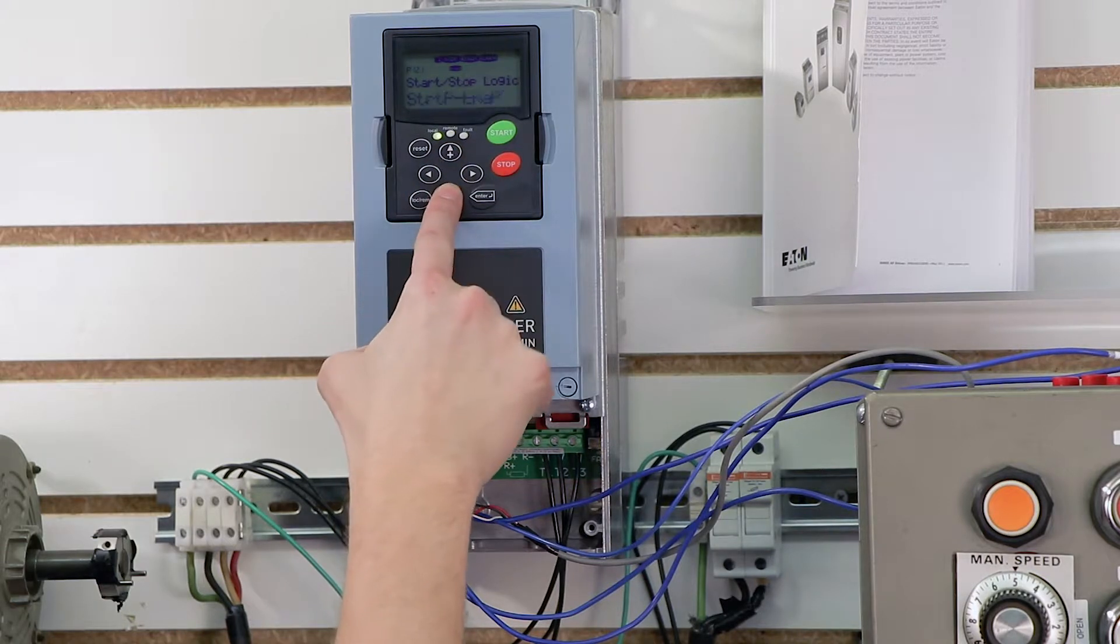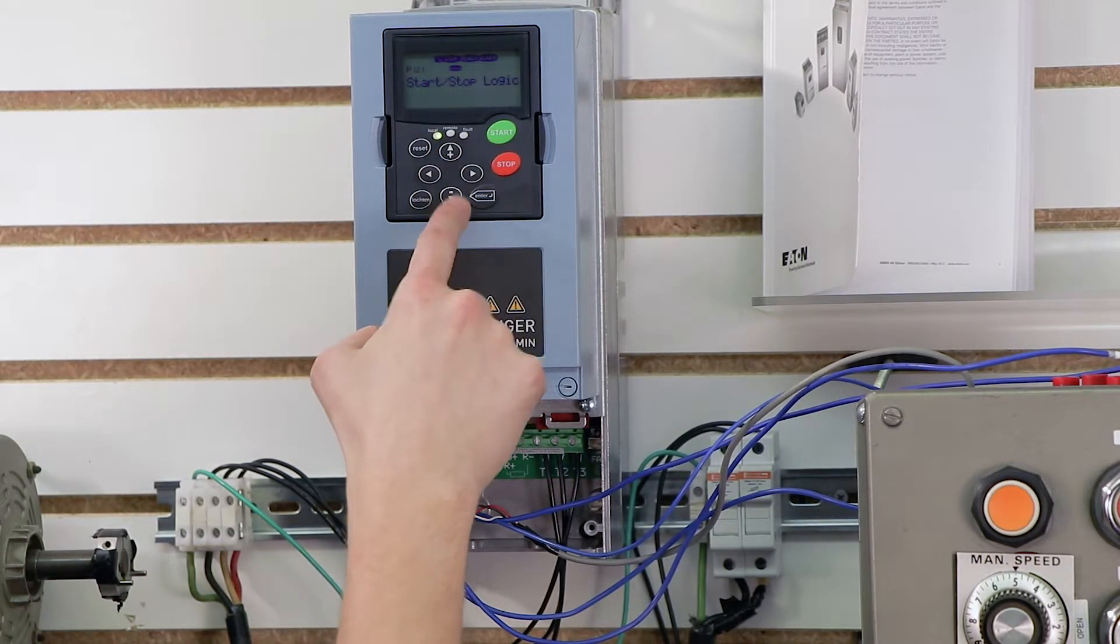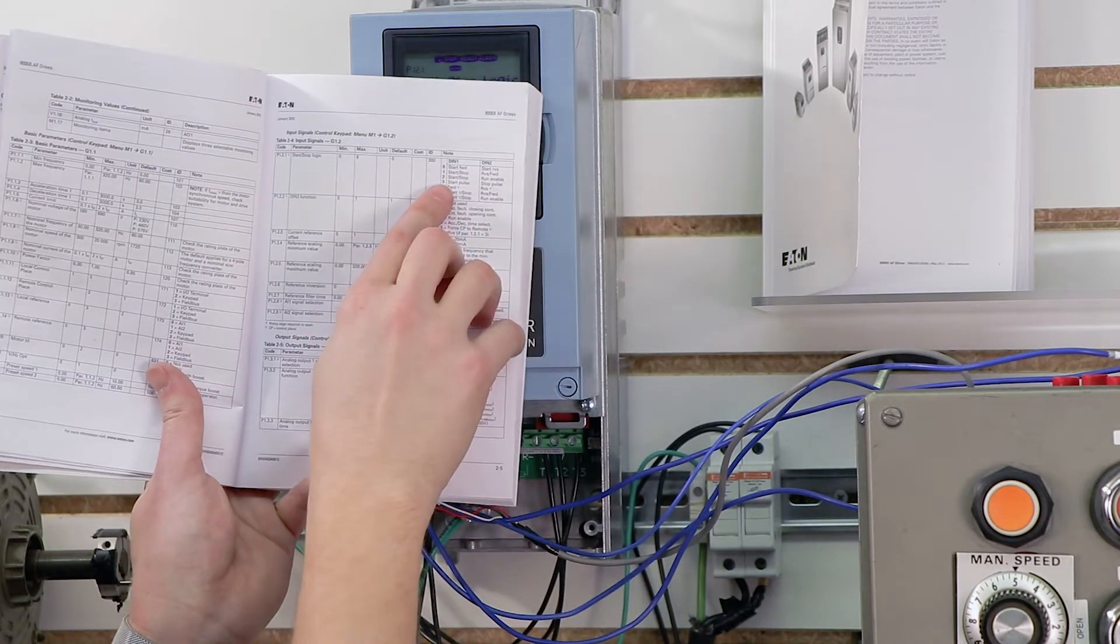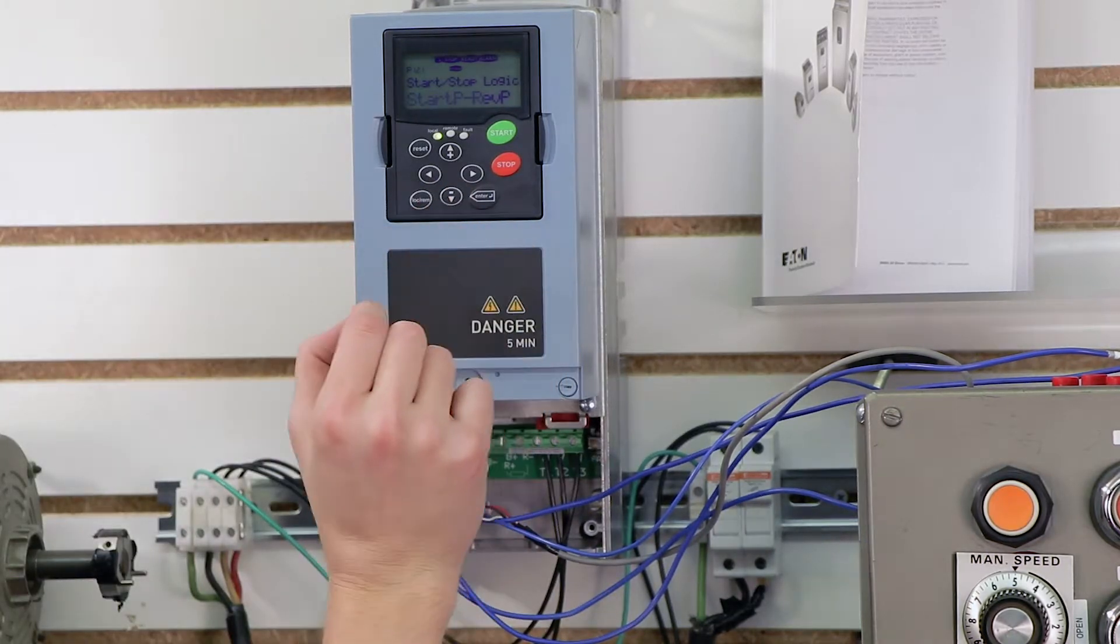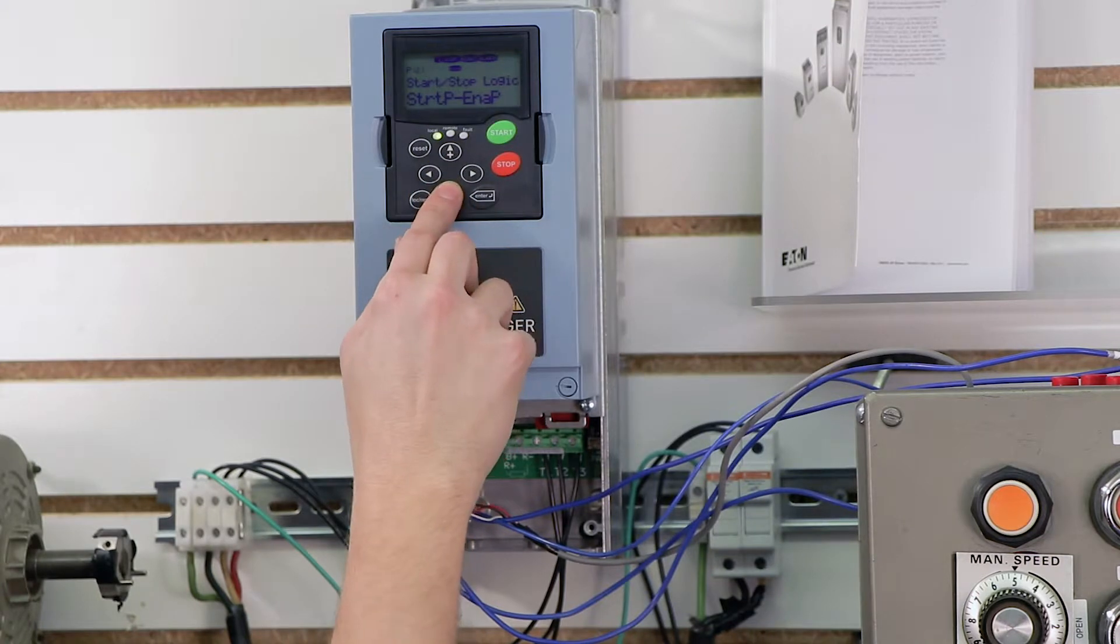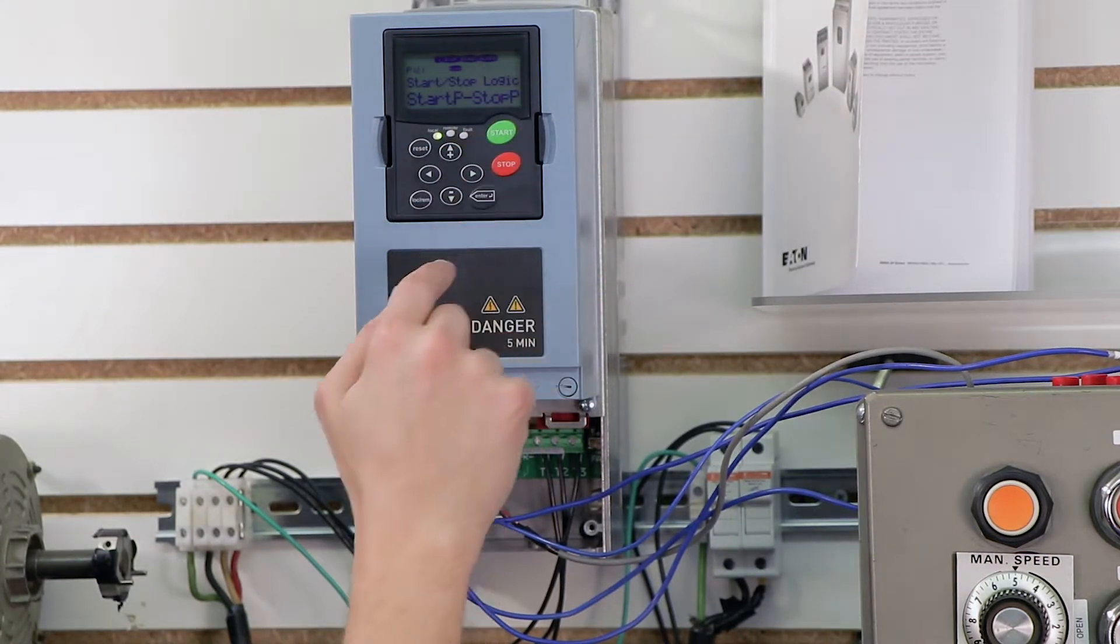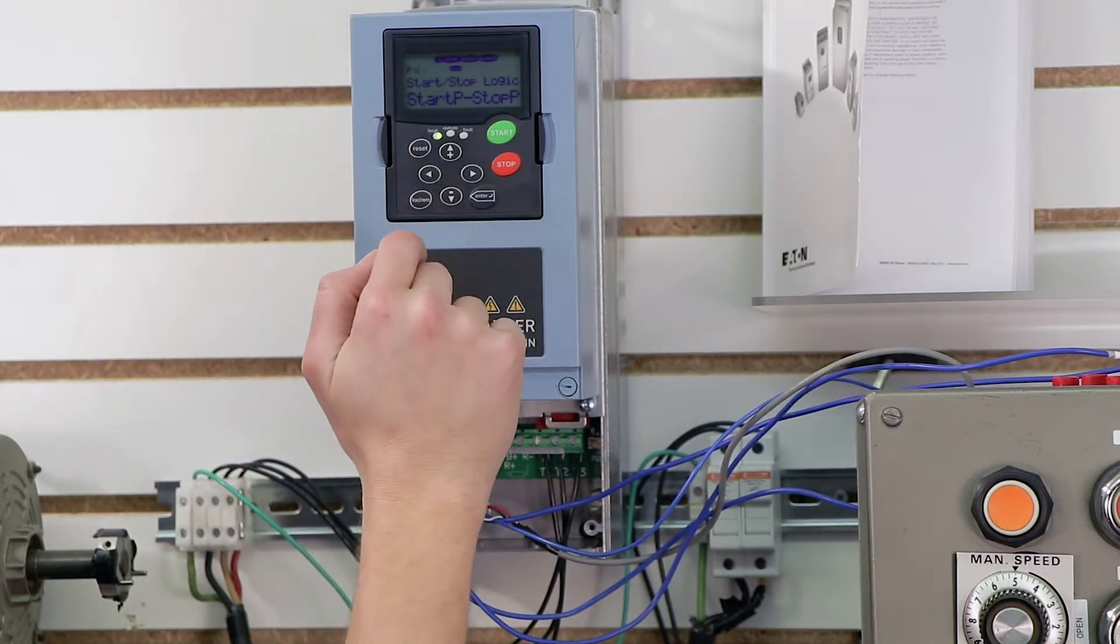By default, it's just standard start and stop, which means you have to have a selector switch, but what we're looking for is on the right here is start pulse, stop pulse, which means a momentary flow of voltage is what's going to start and stop it. So let me go up through here, start pulse, stop pulse, and I'm going to press enter, and so 1.2.1 is done.